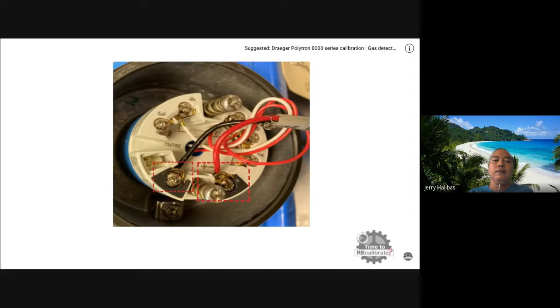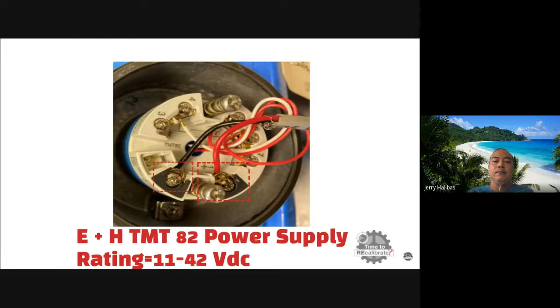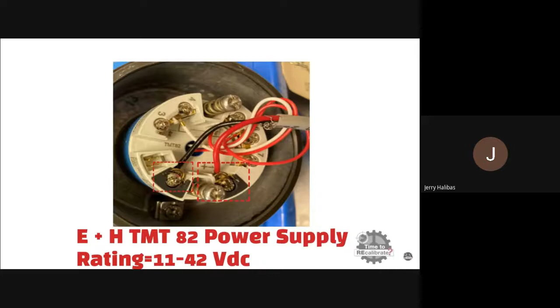And apply a 24 volt DC supply to the temperature transmitter. You can find the power supply rating on the nameplate of the temperature transmitter. For example, this E&H temperature transmitter supports 11 to 42 volt DC supply. Since different manufacturers have different power supply ratings, it is advisable to check the power supply rating of the temperature transmitter before applying supply to it.